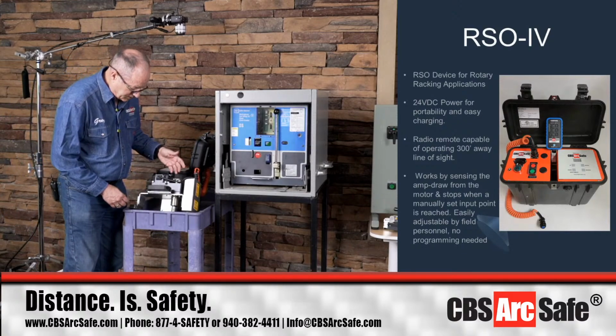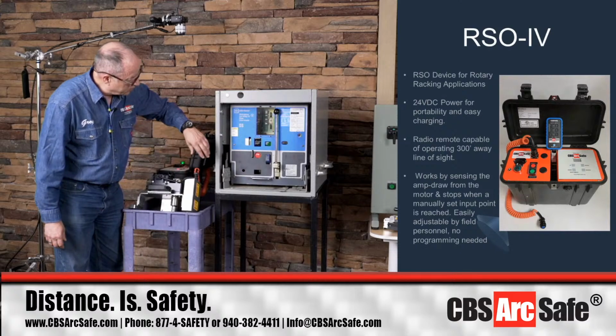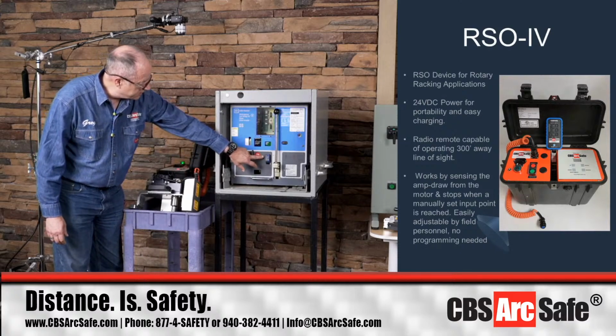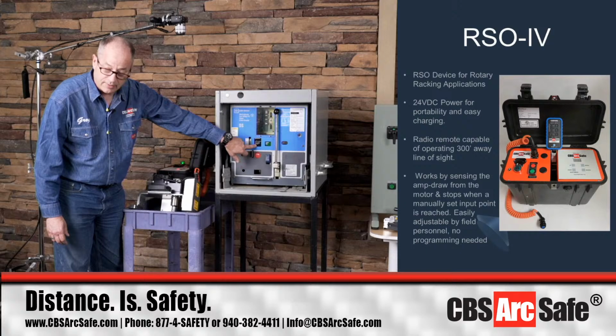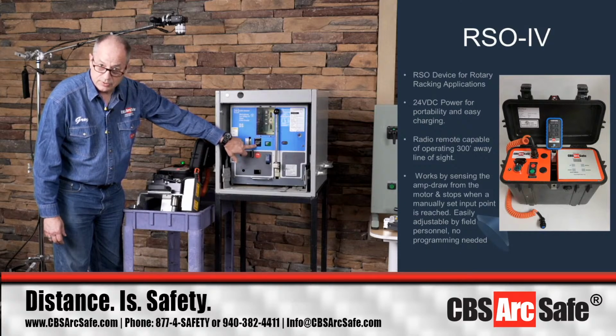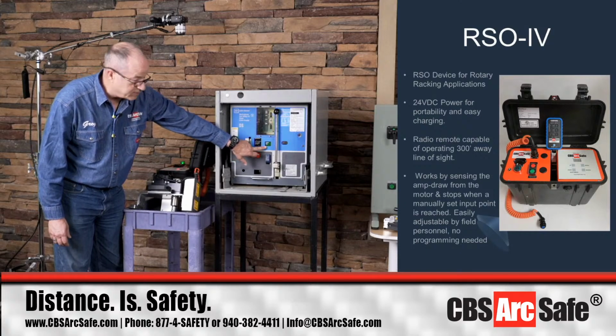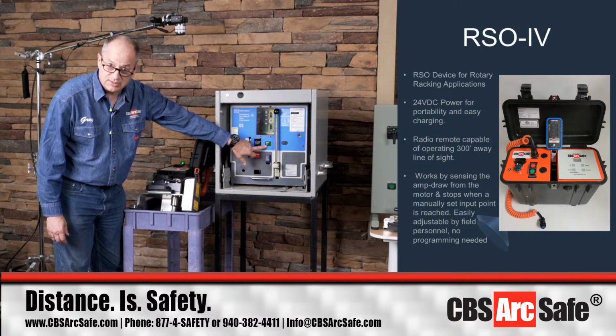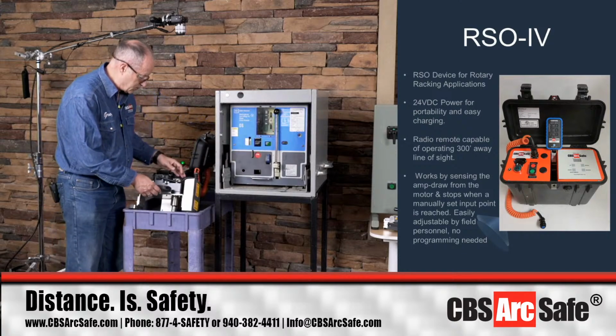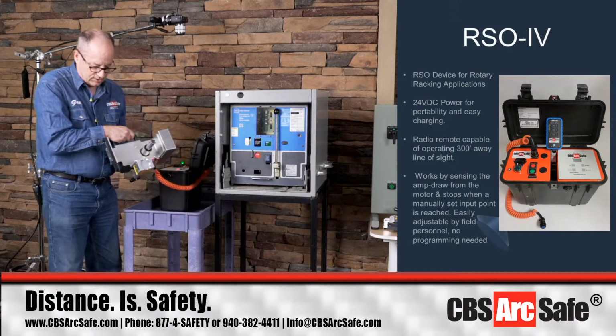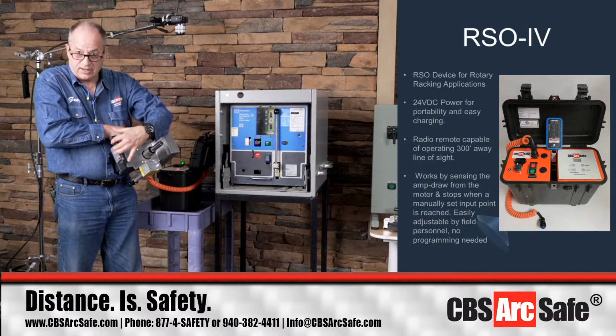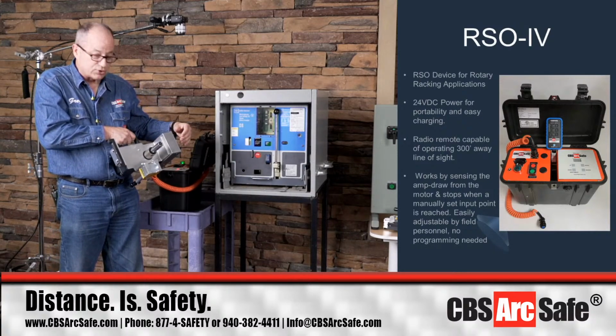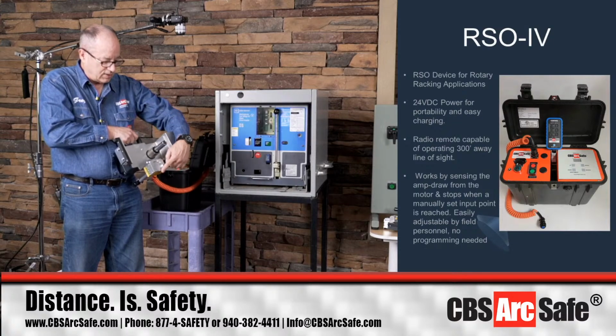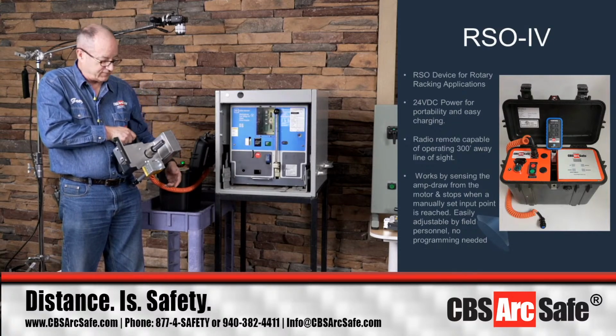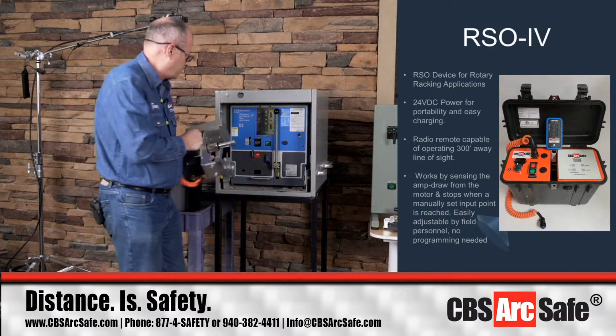So with the RRS-III for the DS, what you have to do is push down the trip button to hold down the access to this. The breaker does have to be in the open position, so we can see that that's there already. And then we simply slide this, and you can see that this is going to sit on the handle, so that's going to give us torsional resistance there for the handle. And we're going to use one magnet here to hold this on the face.